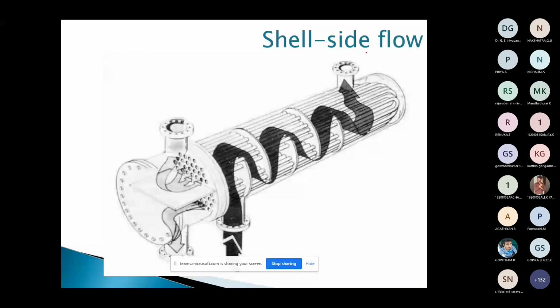So this will give you an idea of how the fluid flows inside the shell and tube heat exchanger. You can see the dark, black color. This is the flow of fluid. This may be either hot fluid or cold fluid. The fluid selection depends on us, which will be discussed in the last slide. Okay, right. This dark fluid flows inside the shell, outside the tubes, whereas the other fluid enters the tube. So that will flow into the tube.